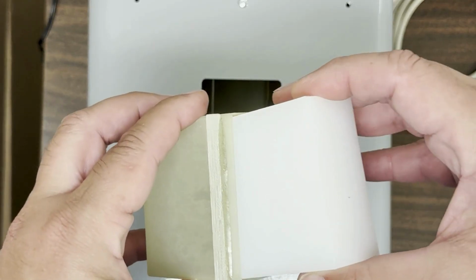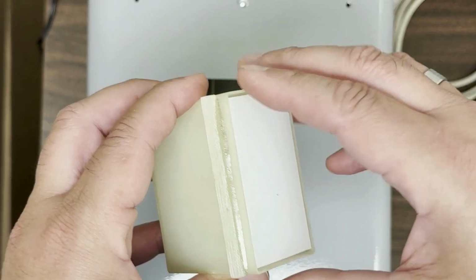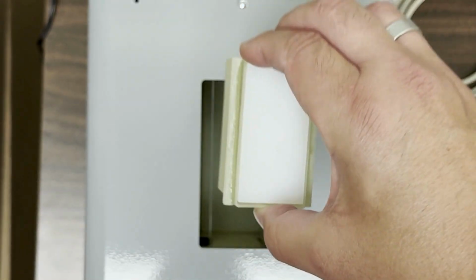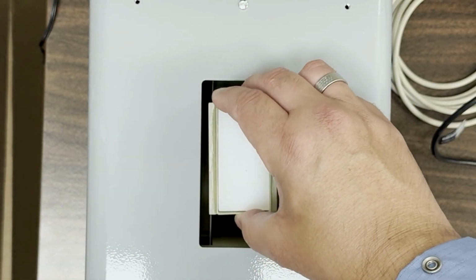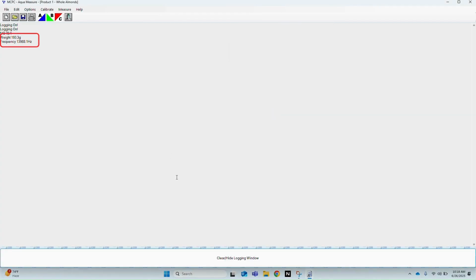That will show up on a screen in a results window, and all you would need to do is verify that those values that are on the screen match the values that are stamped on the block. Weight and frequency will need to match what is stamped on your block. That proves that your MCPC is within factory calibration. So the measure tab here, measure product.